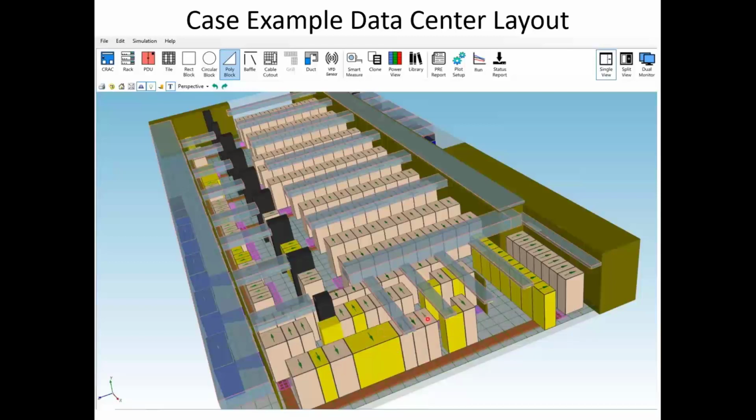And there are other issues here. Classroom style, again, underneath here, if you look closely. So not an ideal configuration. I would argue that this end of the room is probably the most problematic just looking at it. No containment being used here at all, but it is what it is.